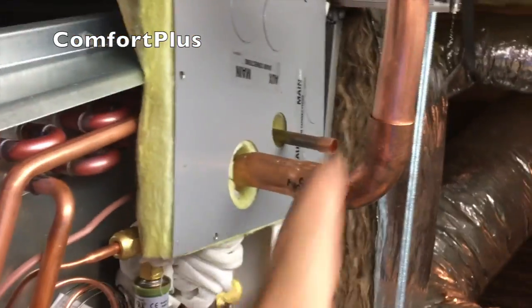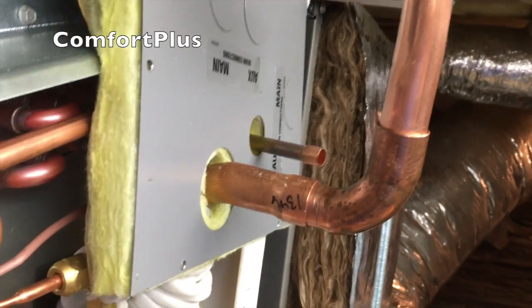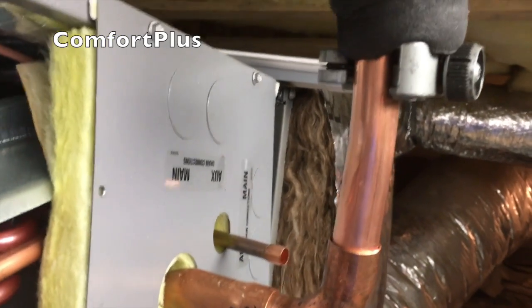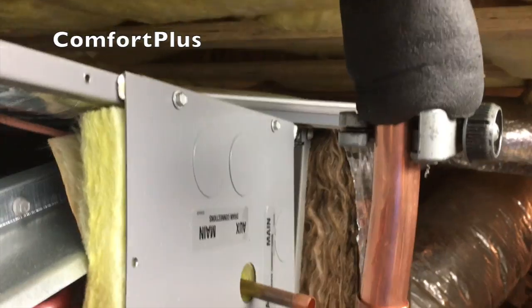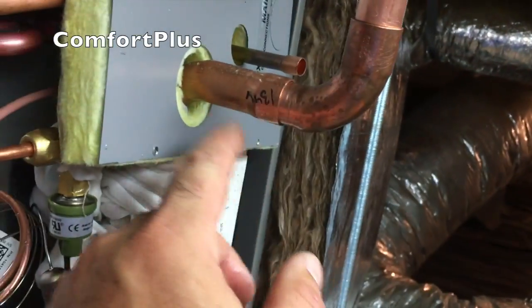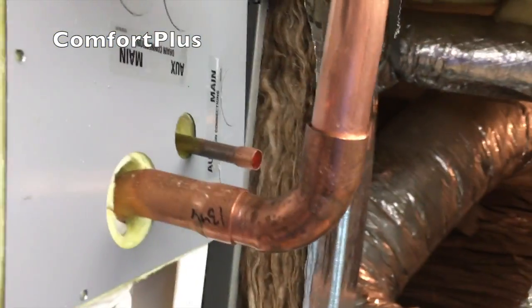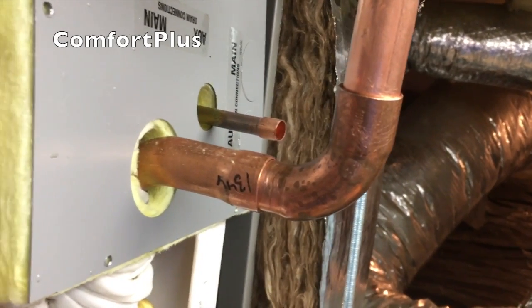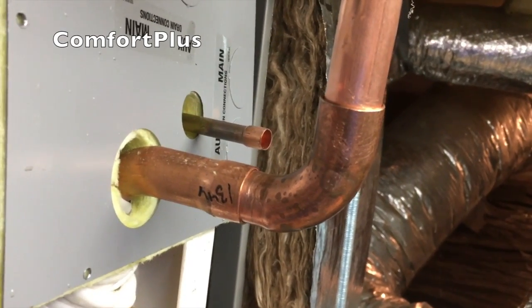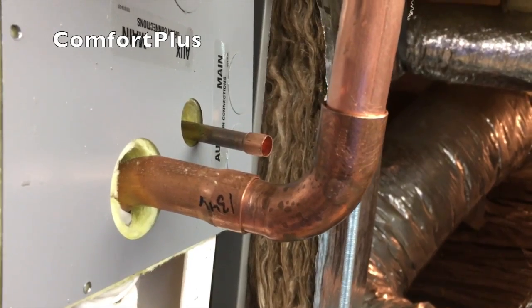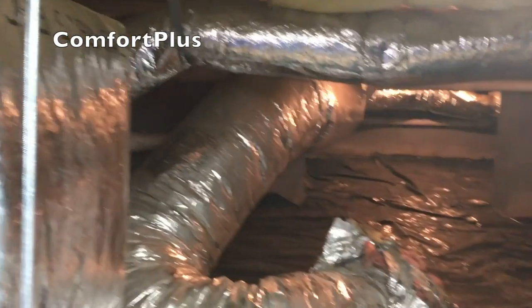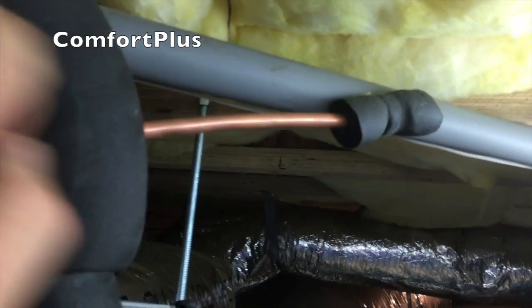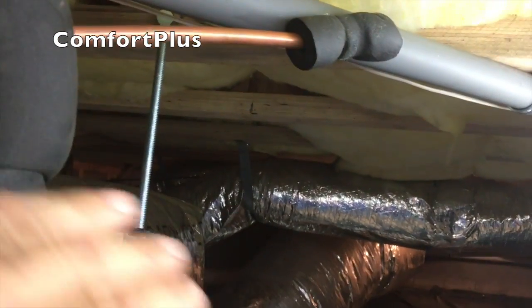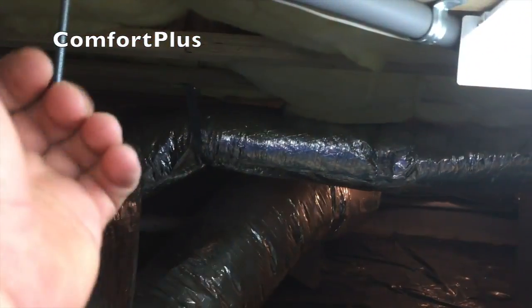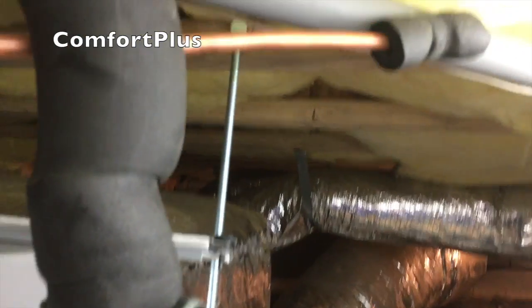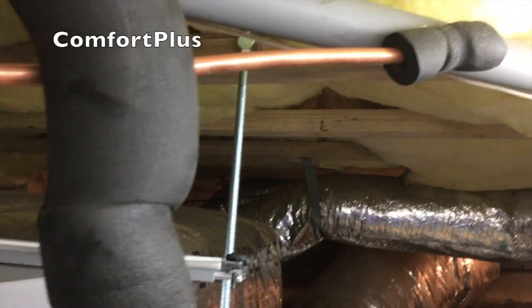But I used a little street L right here. Had to take off about 2 inches pipe in here, so it should be real close to a 50-foot line set. So I've got nitrogen coming through here. I will braze these 2 joints up, and then I will go out and switch the nitrogen to the other side, because I will probably sweat my dryer on kind of horizontal here and then bend it down. It'll just be a lot easier to do without getting the flame up close to the cabinet.